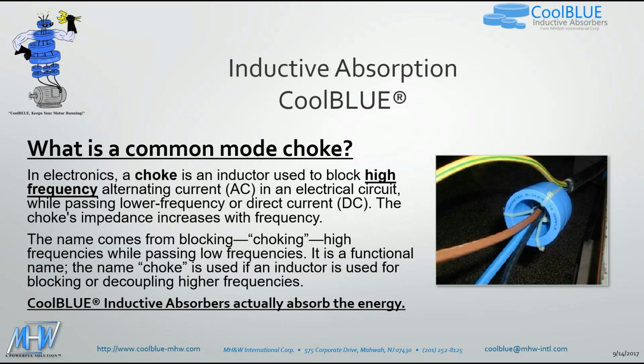What's a common mode choke? A choke is basically an inductor. It's used to block high-frequency alternating currents in an electrical circuit while passing the lower frequencies. In VFD applications, it allows your 60 hertz current to pass through, which is what we need for the motor to operate, but it blocks all those high-frequency currents that cause the arcing and the damage to the bearing, and also the interference to the other electronic devices attached to the system. The name comes from blocking or choking high frequencies while passing low frequencies. It's a functional name. The name choke is used for an inductor used for blocking or decoupling high frequencies, so it's pretty self-explanatory. Just trying to get the idea across that you are choking or blocking these unwanted high frequencies.